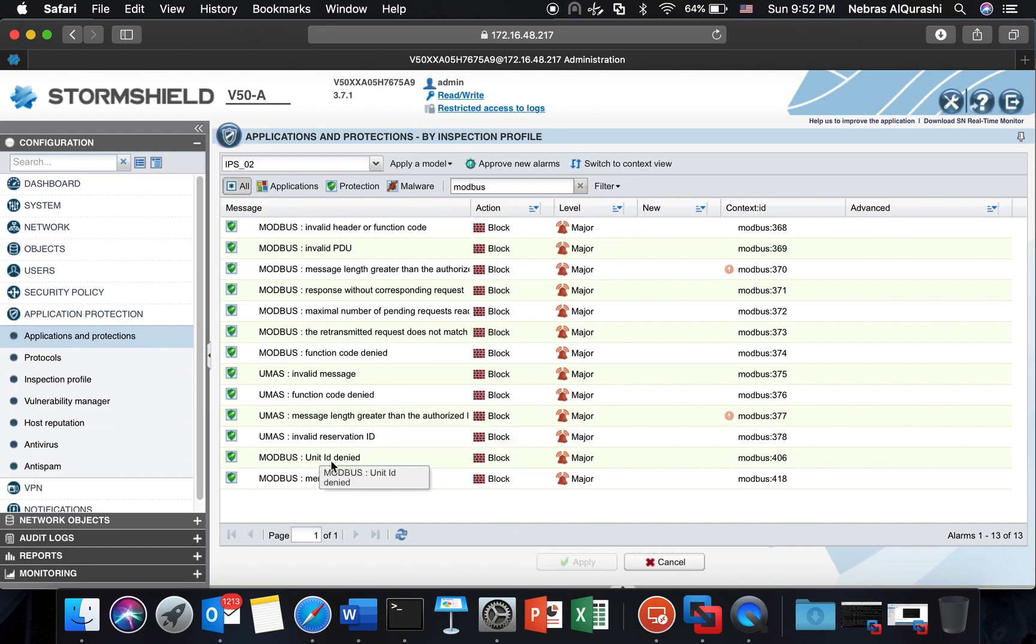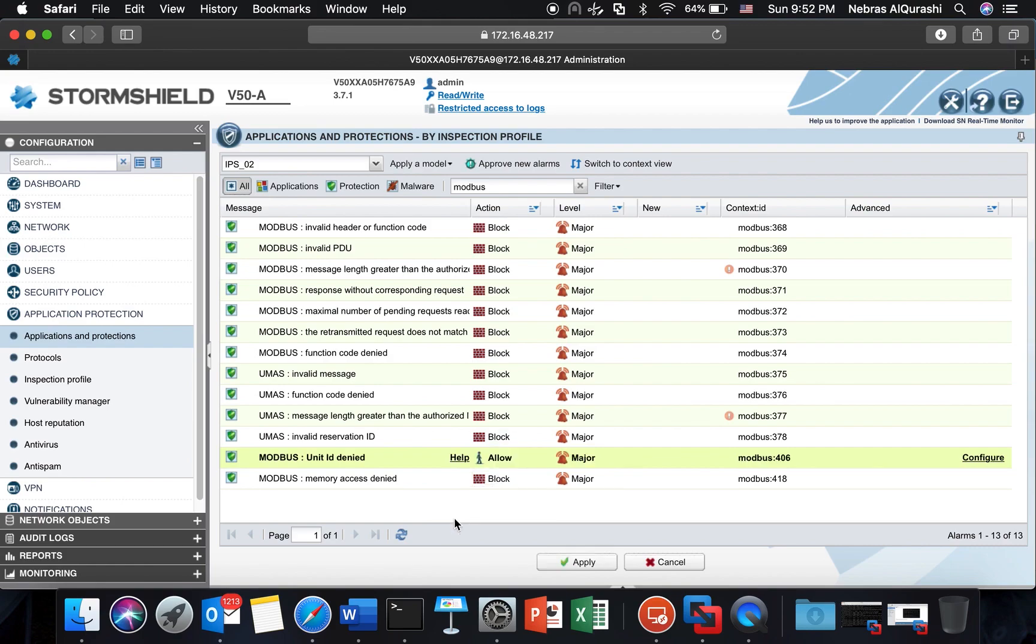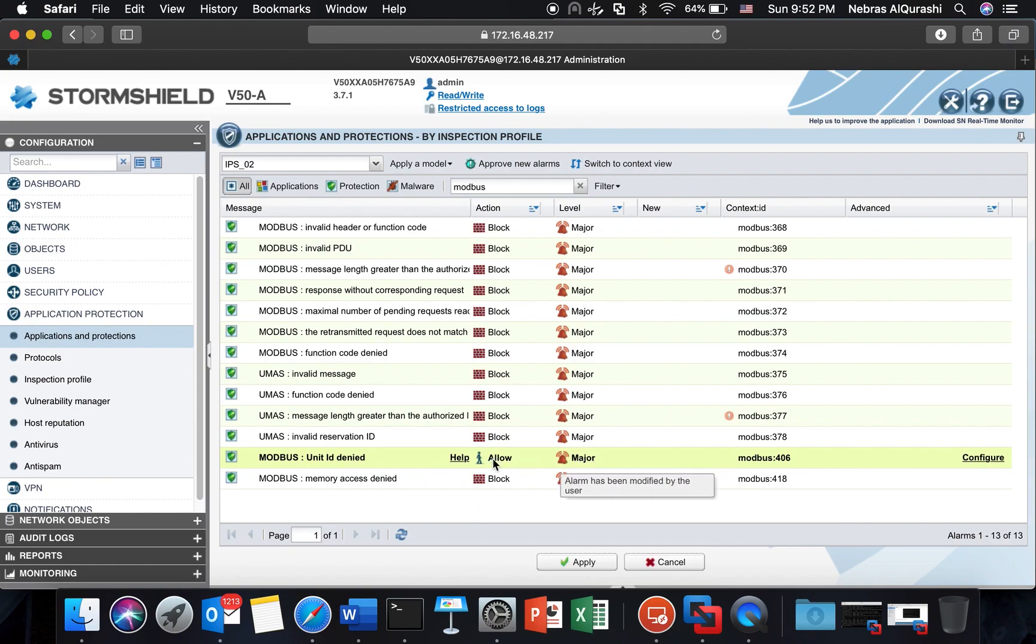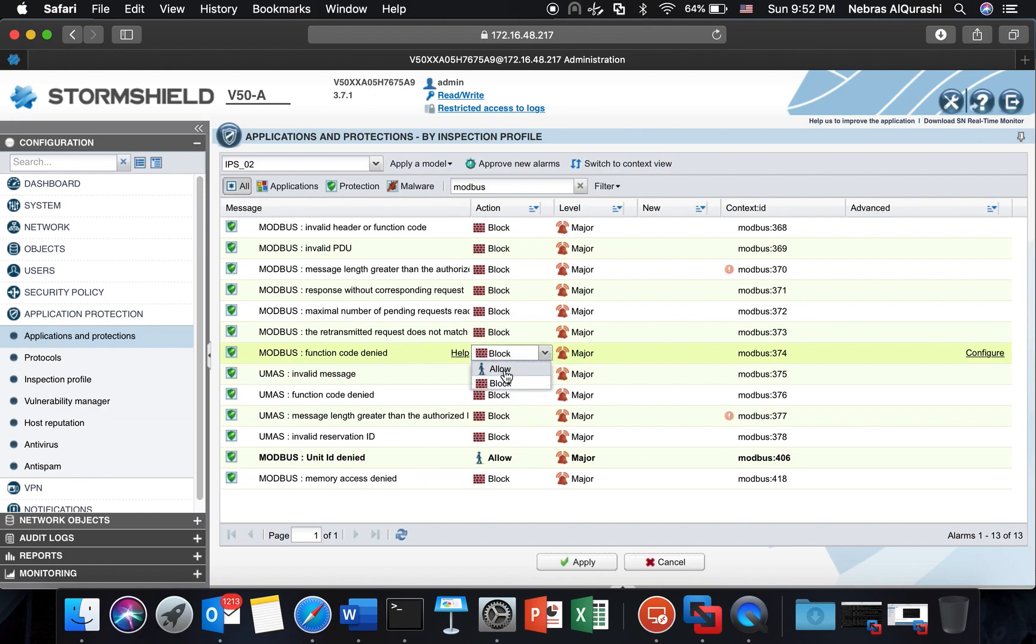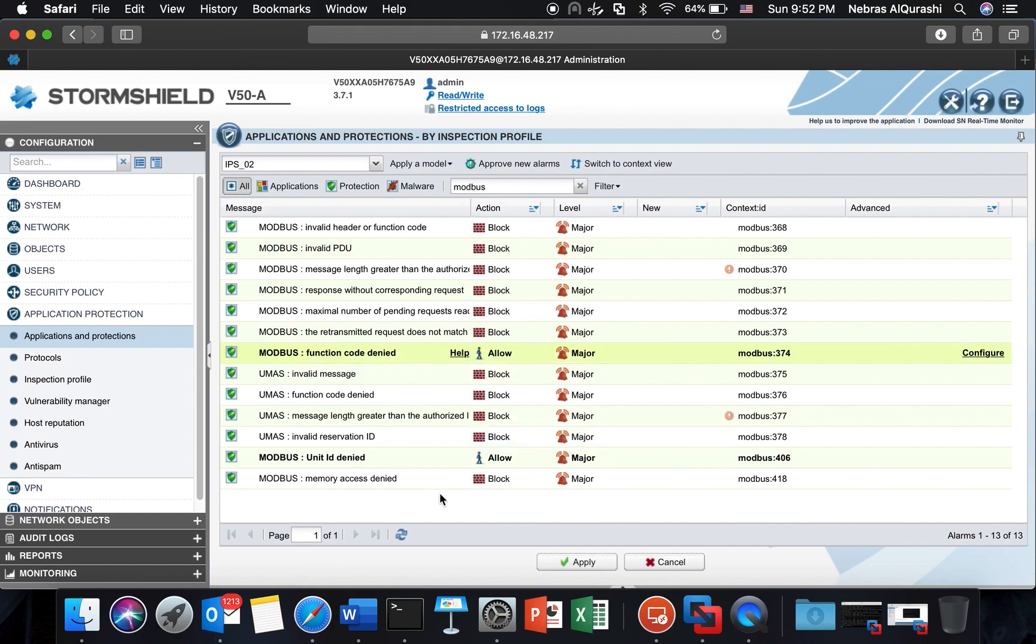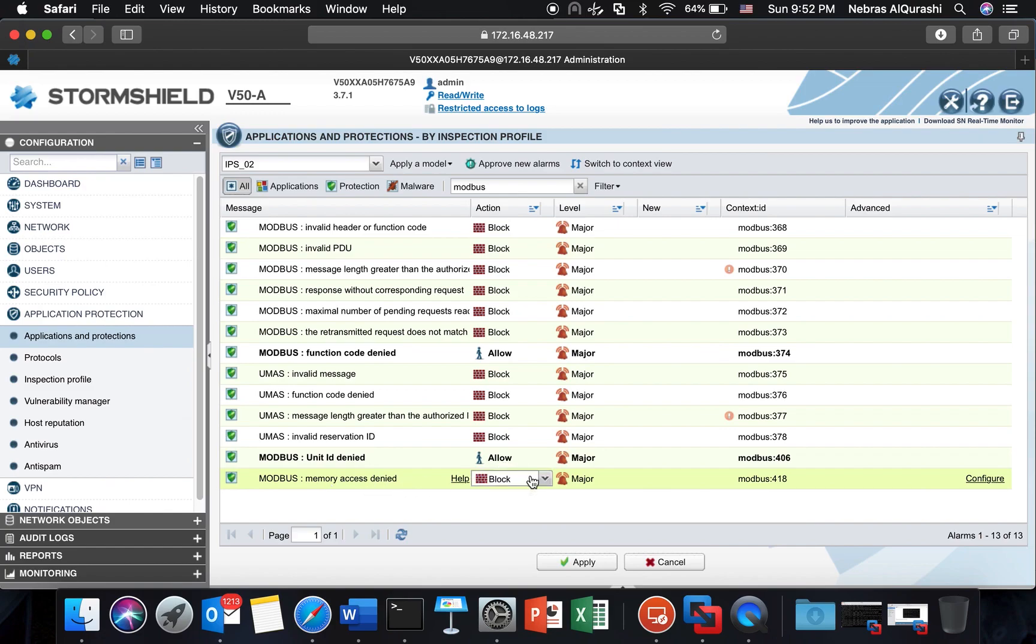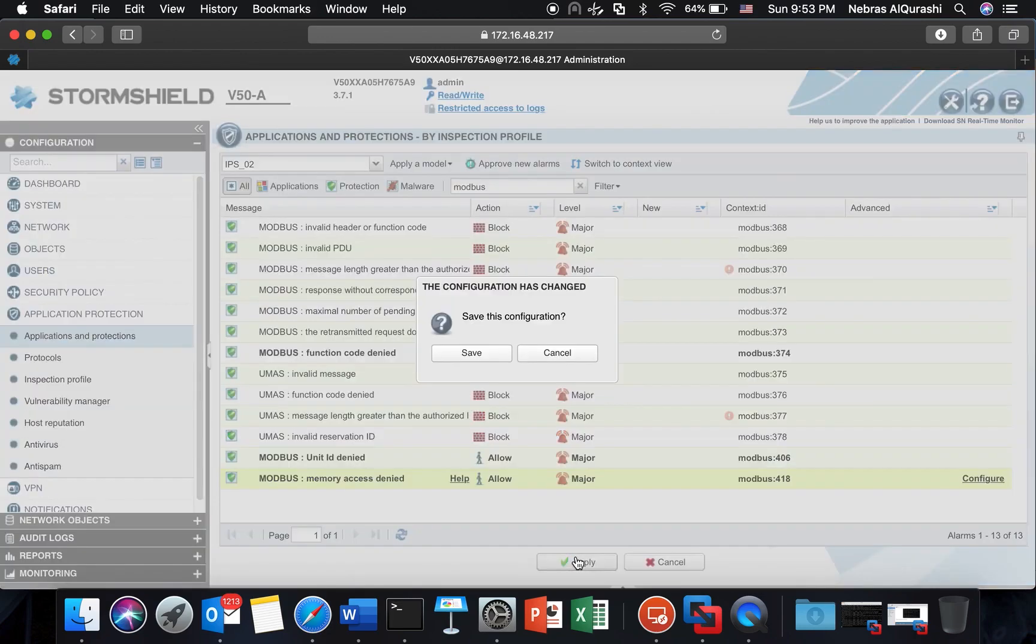I have set the unit ID to empty so it will not match with anything so I want to set it to allow. So whatever the unit ID is there it will raise an alarm as a major alarm but it will not block the connection. The same thing I'm going also to Modbus function code denied and also I will set it to allow although that I have set all the function codes to block but the major alarm I have set it to allow. And the last thing is the memory access denied also the same, so I will set it to pass.